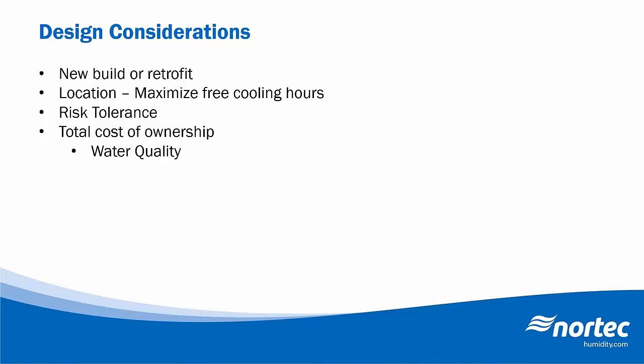Pumps on the high-pressure nozzle systems will need to be rebuilt or replaced every few thousand hours. Transducers on ultrasonic units will need to be replaced. So definitely you have to keep in mind the maintenance requirements on these types of systems. So in addition to that, you do also want to consider the need for treated water if you're looking at an atomizing nozzle system or an ultrasonic unit. So definitely there's the added cost for the water treatment equipment itself, as well as the water usage.